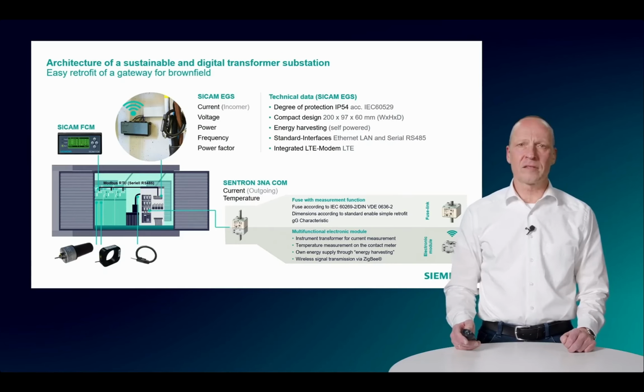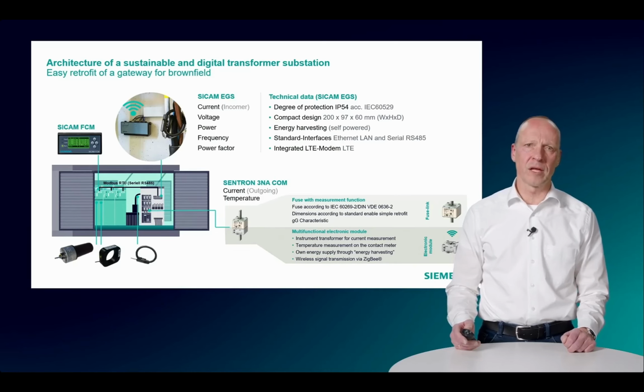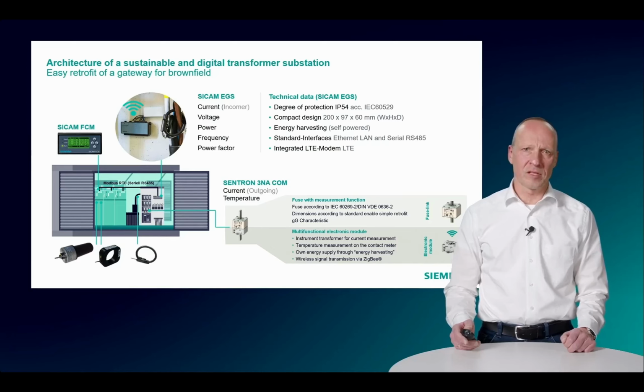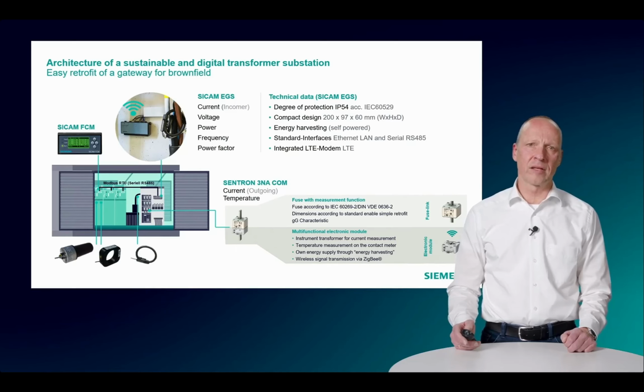Retrofitting of external low power CTs and VTs on the medium voltage ring main feeders together with the SICAM FCM gives transparency also about voltage and current from the medium voltage side. As the EGS is self-powered and provides an integrated LTE modem, connection to SCADA systems and/or to the cloud can be done with less efforts.